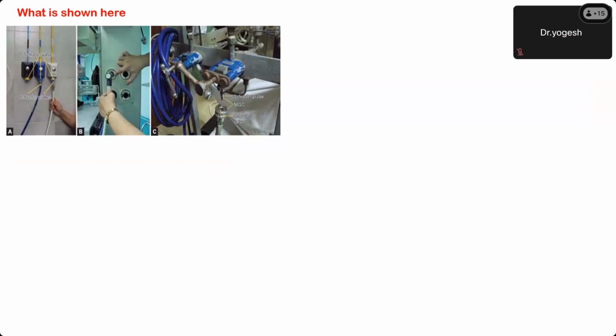What type of connector is that B? Is it like A or is it different? It is non-interchangeable screw threaded. It is NIST from a ceiling pendant. Okay. Whereas the first one is a wall mounted, as is shown in the first picture, it is a wall mounted self-sealing or Schrader valve. It is also written very faintly, the Schrader valve and Schrader probe.